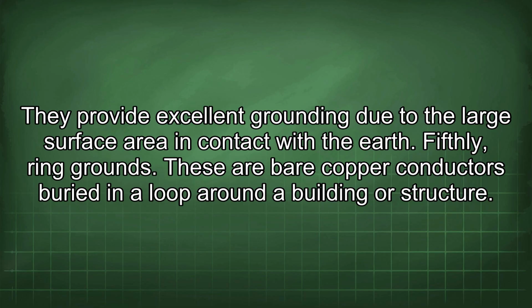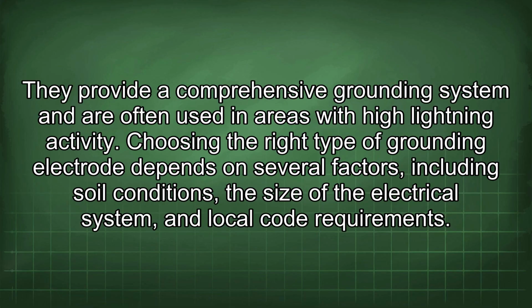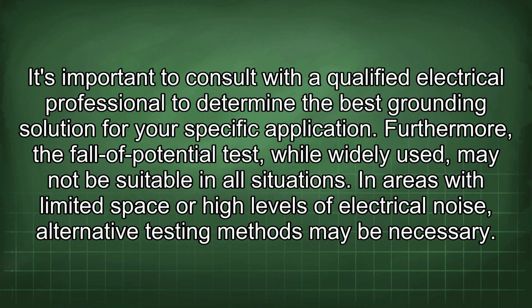Fifthly, ring grounds. These are bare copper conductors buried in a loop around a building or structure. They provide a comprehensive grounding system and are often used in areas with high lightning activity. Choosing the right type of grounding electrode depends on several factors, including soil conditions, the size of the electrical system, and local code requirements.